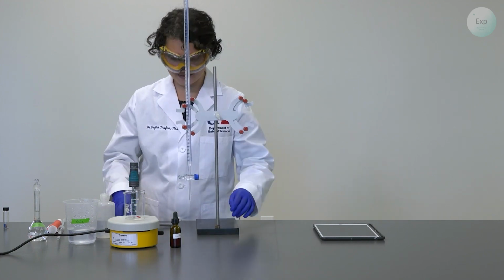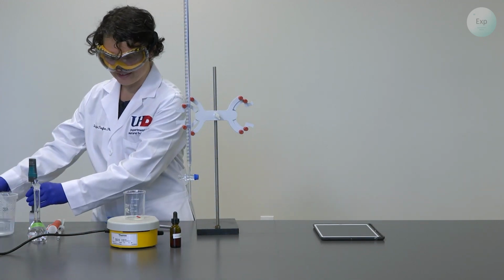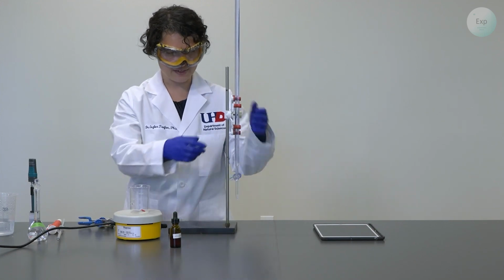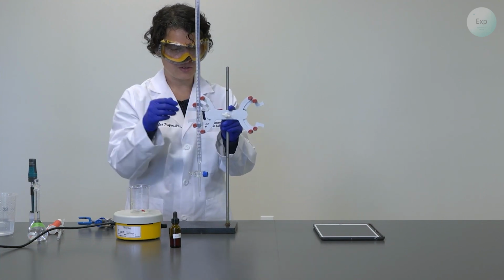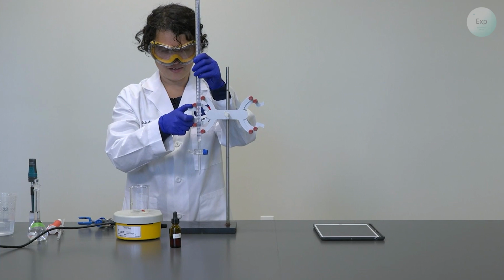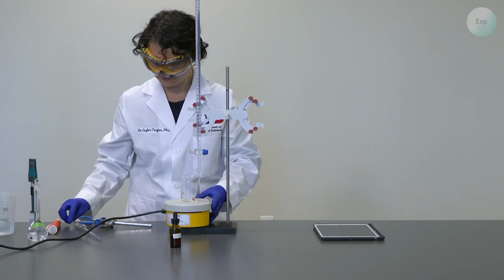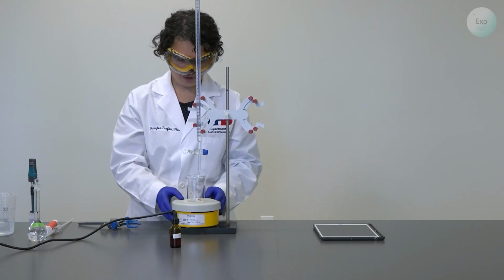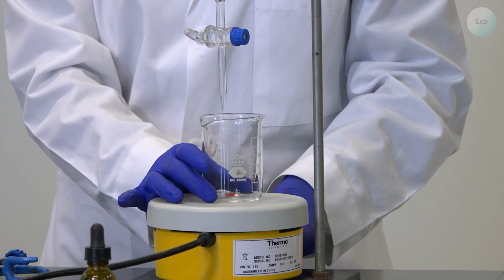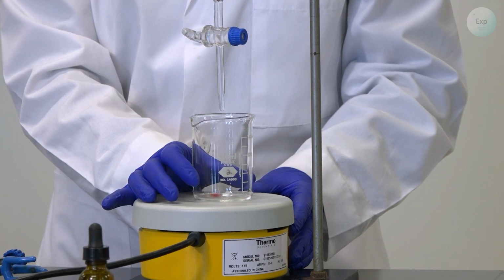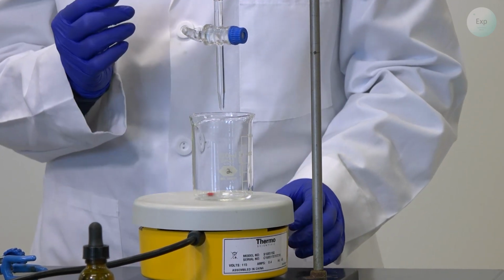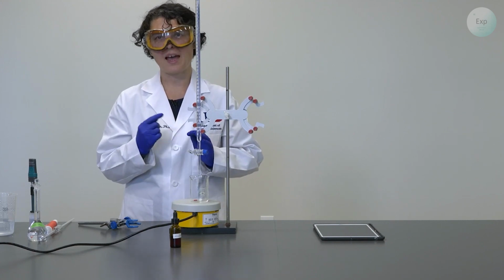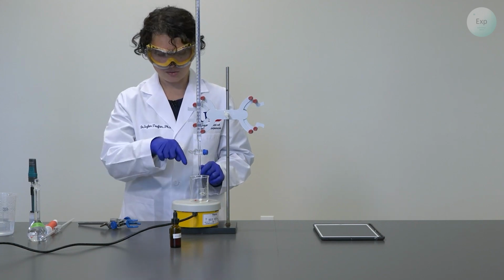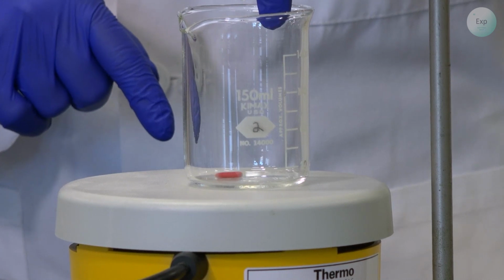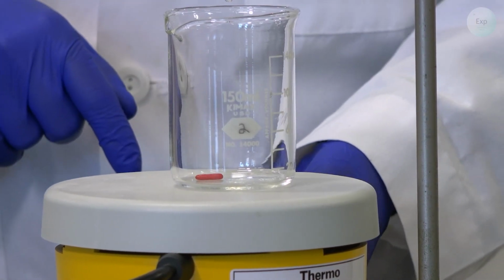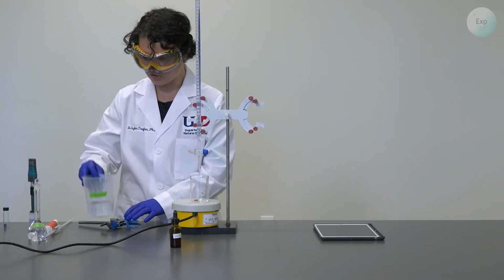The first thing that we're going to do is make sure that everything is in the right place. First, we're going to bring in our stand, and we're going to position our burette so that it will be above the beaker that has the stirring rod. We will turn on the stirring to at least medium-high to identify the location of the stirring rod as it is going to mix our solution. This is important because we don't want the stirring rod's rotation to accidentally hit the very sensitive pH probe. So if it mostly stays in that position, our pH probe has to be somewhere else inside our beaker. And with that, we can turn this off and we can prepare for the insertion of our pH probe.